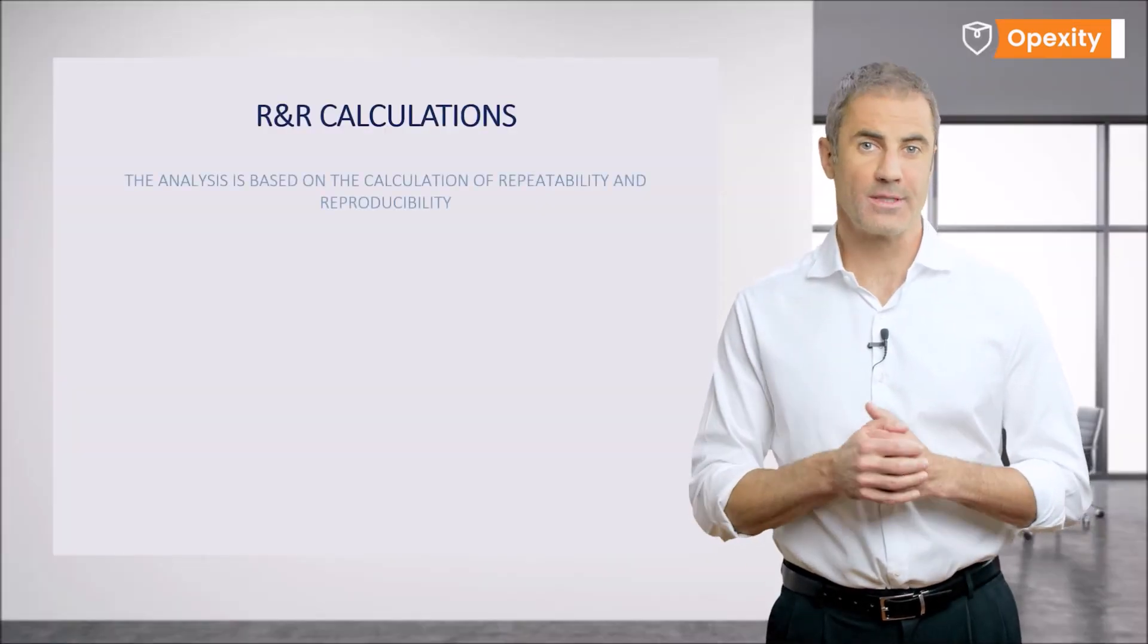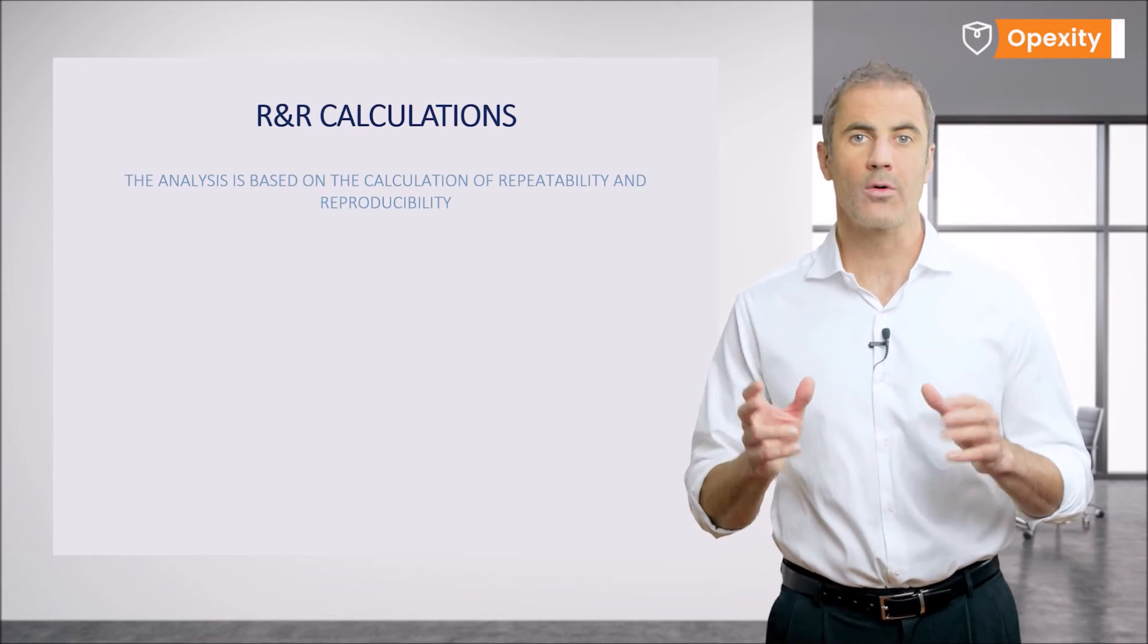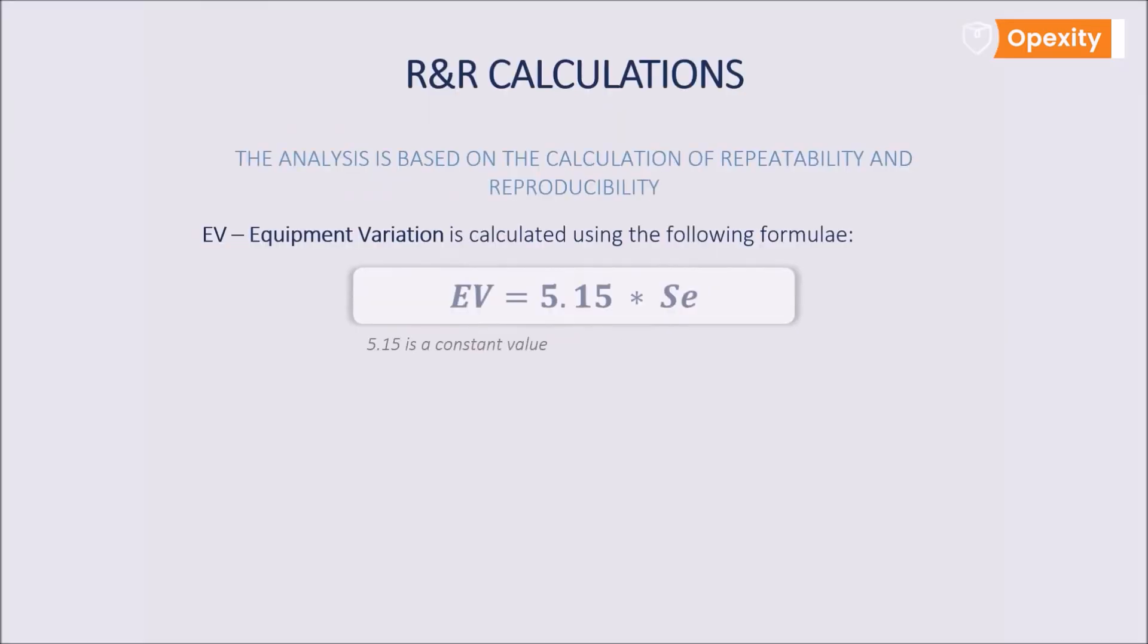Finally, we can calculate the repeatability, the so-called equipment variation EV. Here we apply the standard formula by multiplying the value of the previously calculated standard deviation SE by the constant 5.15, where 5.15 times SE represents 99% of the measurement results for a normal distribution.